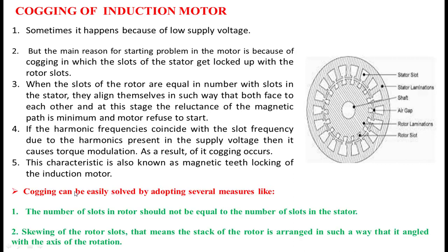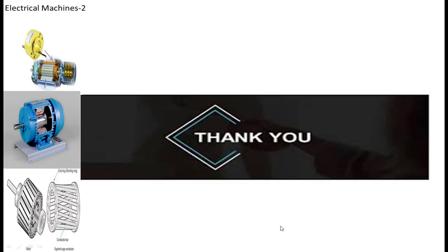Cogging can be easily avoided by adopting several methods: the number of slots in the rotor should not be equal to the number of slots in the stator. Another method is skewing of the rotor slots — the rotor stack is arranged so that it is angled with the axis of rotation. Thank you very much. If you have any doubt, you can ask me directly or in the comment box of my YouTube channel, and I am always welcome to answer all your questions.